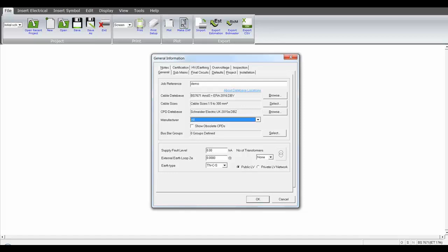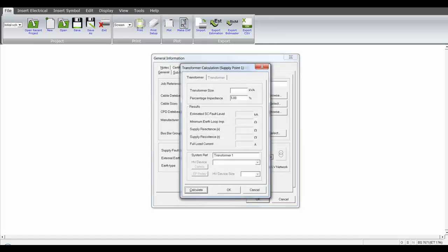Starting off with the supply fault level and external earth loop impedance, you can enter these values from measured values on site or local electricity board information, or you can set up transformer information where you type in the kVA rating of the transformer, the percentage impedance, then perform the calculation, and that will work out the estimated short circuit fault level along with the minimum earth loop impedance, the reactances and resistances, and the full load current that can be generated from the transformer of this size.